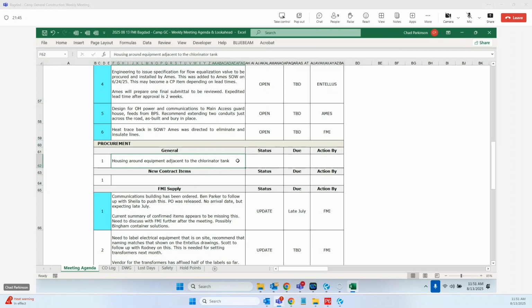Yes, and I'm guilty, so... that's not... something, the building holds the chlorinator equipment that delivers the chlorine to the static mixer. The chlorine analyzer, of course, is mounted over the chlorine contact tank to measure the residual chlorine, which sends a signal back to the pump inside that building, with that control loop that tells how much chlorine to feed. However, the reason for the recent change was we weren't sure what we would need for that chlorine analyzer, for various reasons, because the instrumentation at the time wasn't clear from both manufacturers.